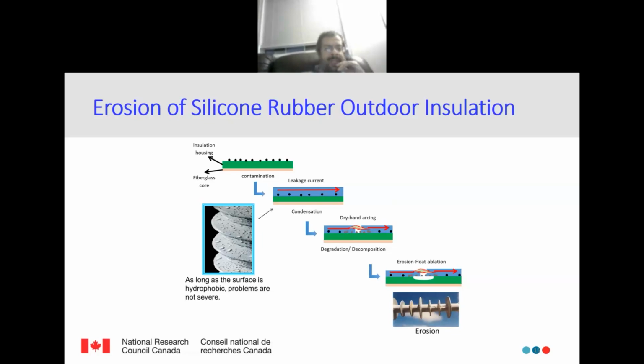Now, here is a demonstration showing the lifetime of these silicone rubber insulators. As I said, they age with time. In a country like Qatar, we have very high ultraviolet radiation. The UV radiation ages those coatings, and gradually they start to lose their hydrophobicity. Then they are easily wetted, and you have leakage current. Once you have leakage current on the surface, certain parts will have higher current density than others, so you will start to have dry bands. These dry bands have very high electrical stress on them, which leads to what we call dry band arcing on the surface, and this dry band arcing leads to the erosion of the material.